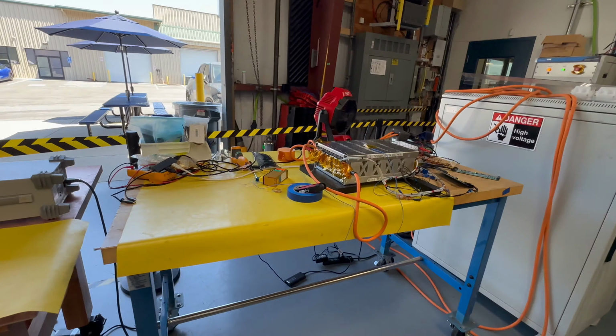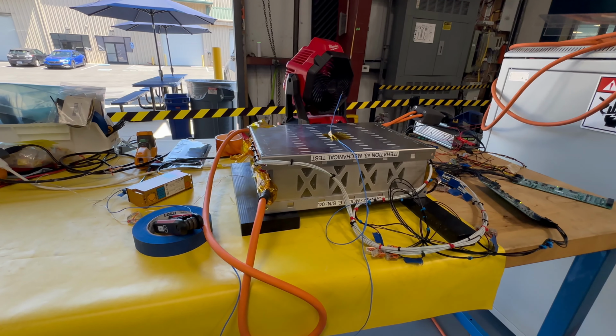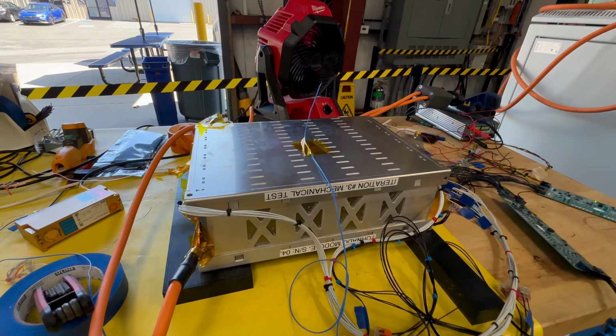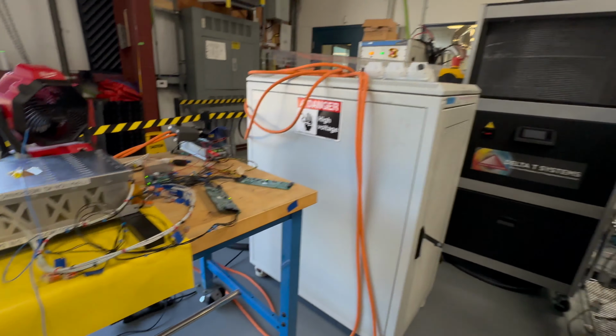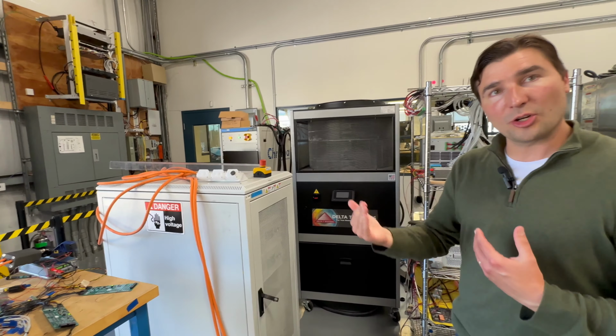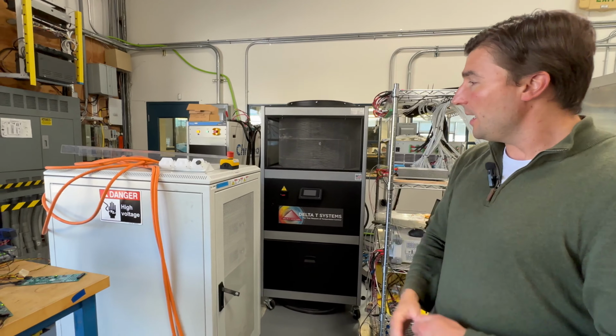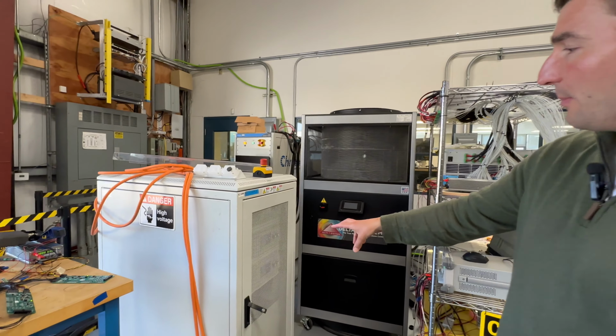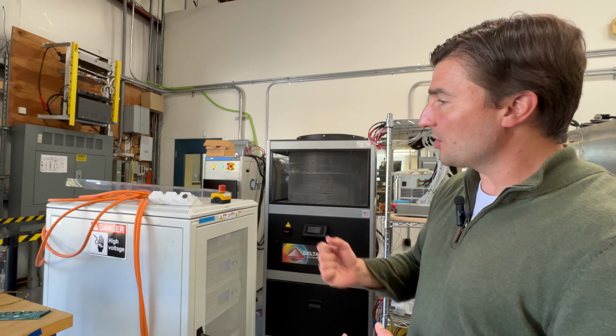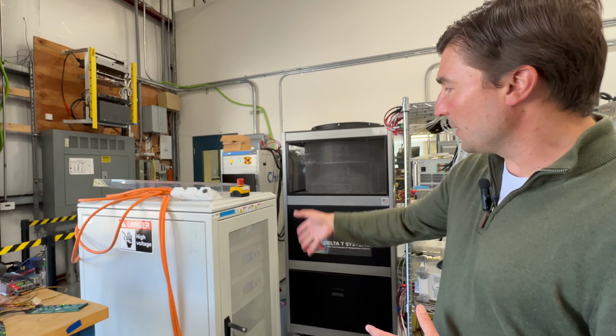This is a battery module under test, basically seeing how it performs thermally. We use a variety of different cyclers here. We have a module level cycler that's grid interactive, which means it charges and discharges actively to the grid. And then we have a 1,000 volt, 60 kilowatt bidirectional supply, so we can charge and discharge from the grid up to 1,000 volts with this piece of equipment.